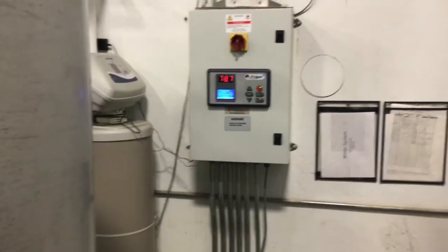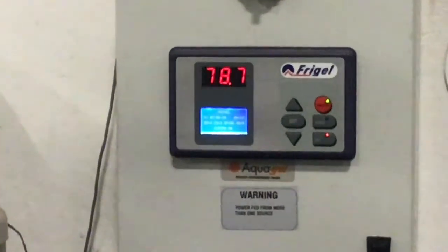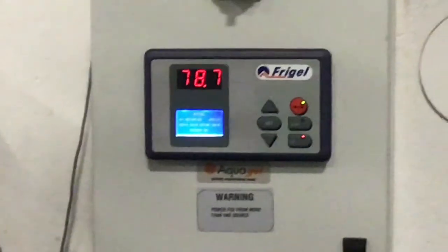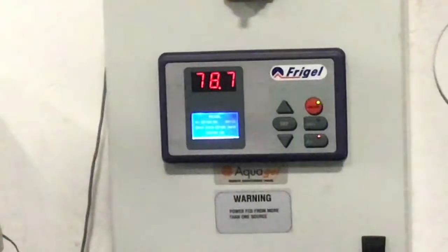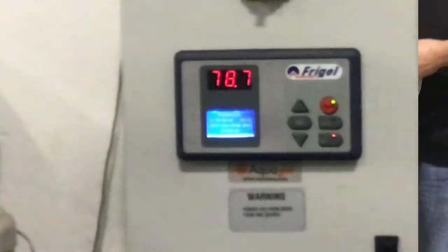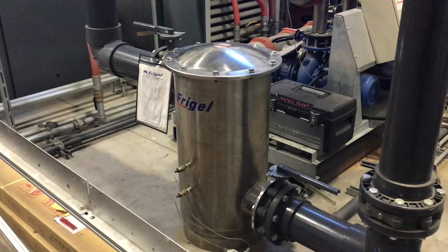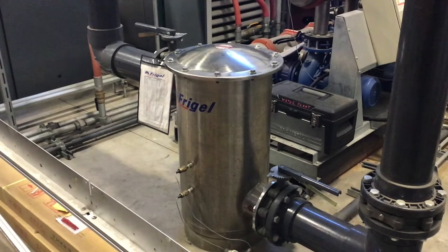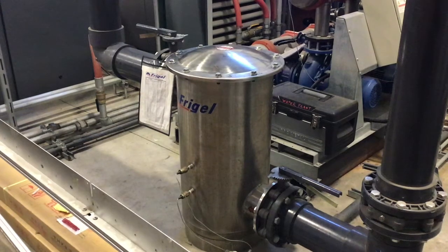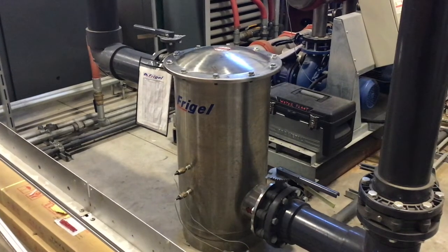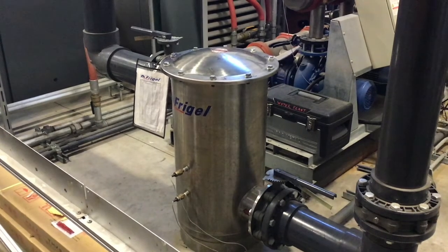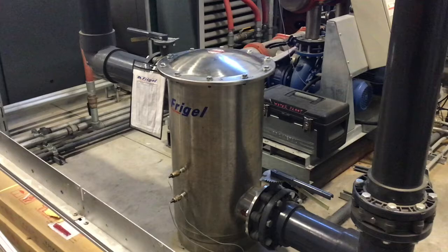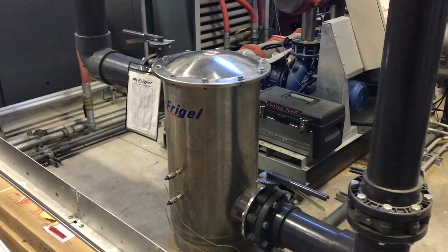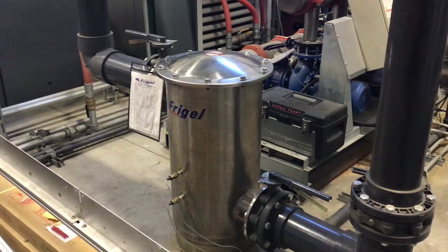A lot of systems will be connected to the main control logic and will tell you when that PSI differential has occurred at a level that's a preset point. But if not, you want to have that individual filter element actually on the unit itself. Here you see it in the front. You see a high and a low pressure differential, and then you see the notes off to the side of when those elements that you saw a little bit ago, when that media is changed out. Very important part of your system so that you get complete and continuous water flow through the plant.